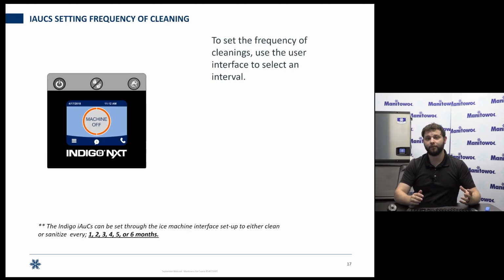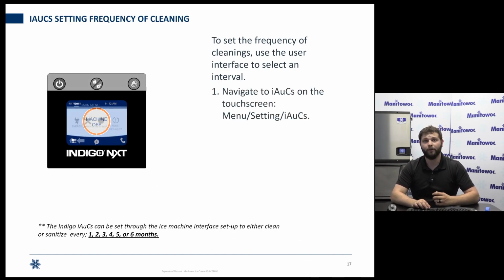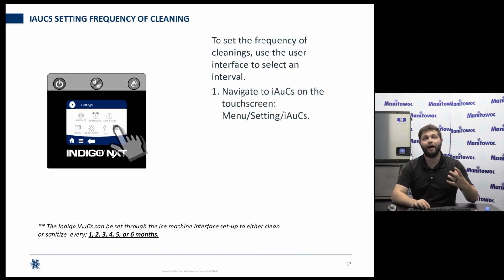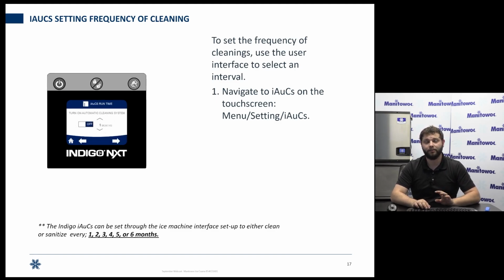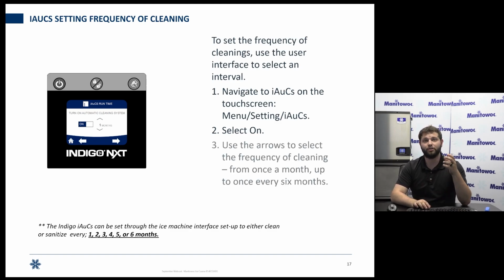Okay, so since we're in this off state now, we want to set up the actual interval between each cleaning cycle that it automatically does. Like I said, we have the option of 1, 2, 3, 4, 5, and 6 months of cleaning intervals that we can decide. So we're going to hit that menu button, we're going to go to settings, and then we're going to get iAuCS. And then in this area, this is where we can set up how many months we do it. So we're going to hit that on button, make sure our iAuCS system is turned on, it's ready to use, and then we'll use those arrows to choose between 1 to 6 months.